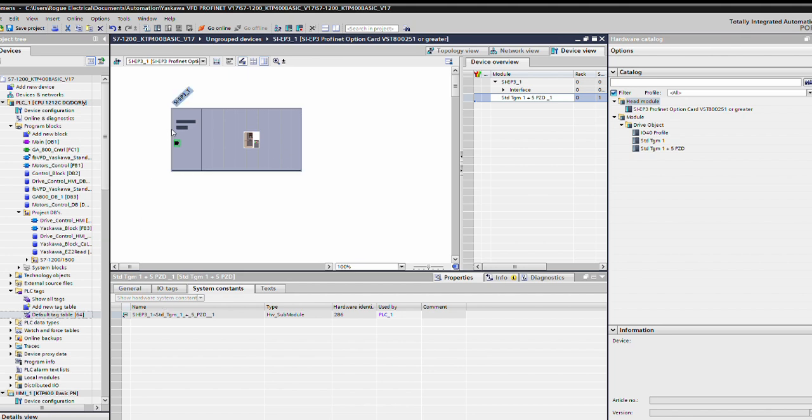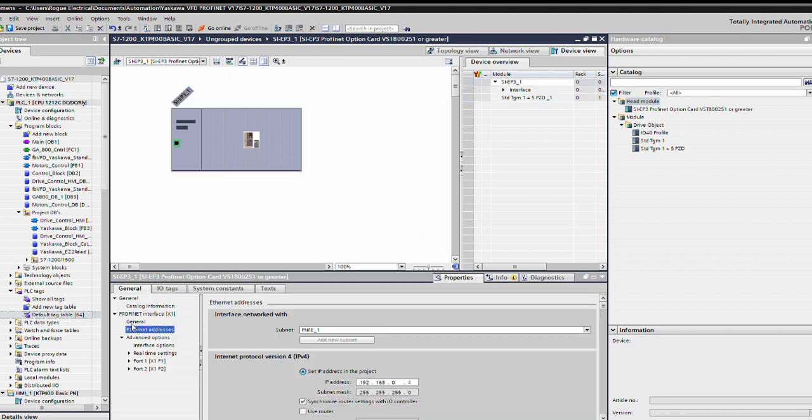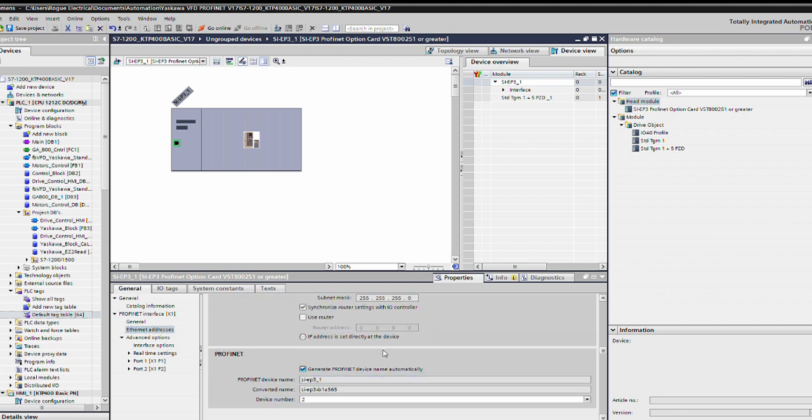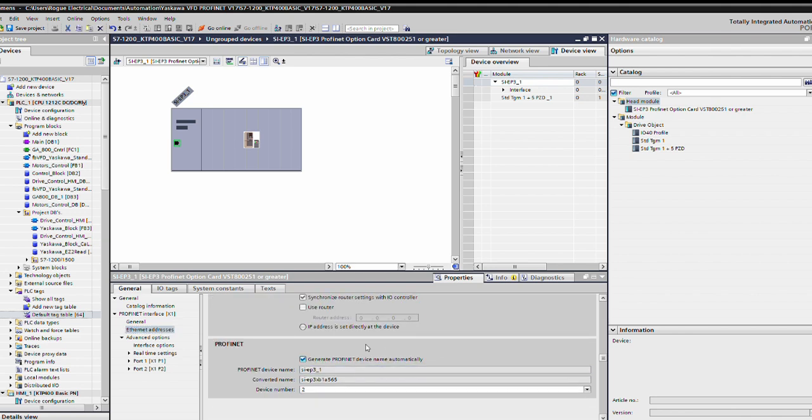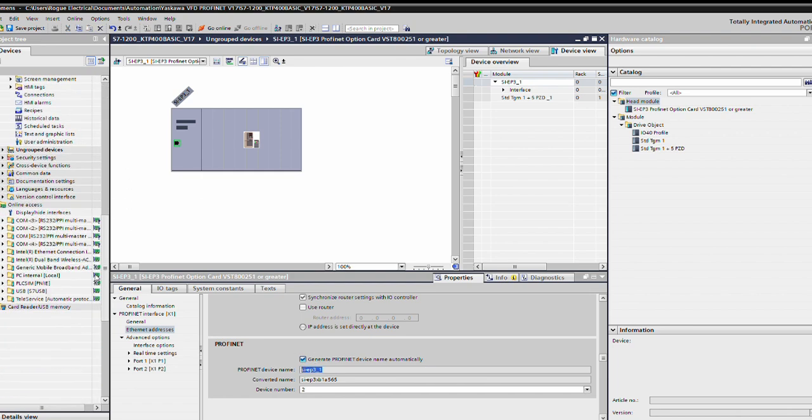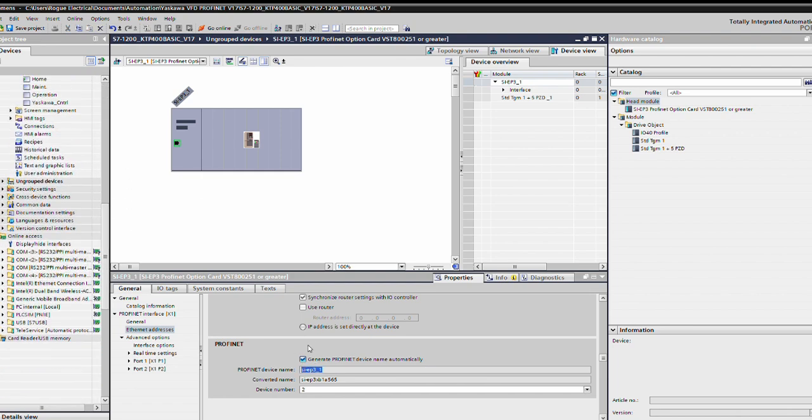We're going to double click on this. Here is your Ethernet address 192.168.0.4. Your ProfiNet name of course is going to be down here. Now if you select that generate ProfiNet device name automatically, this is the name that you will need to copy paste into the window over here. So if I was going to do it again, I'm going to hit copy, go online, and paste this into that little window and assign that device the ProfiNet device name.